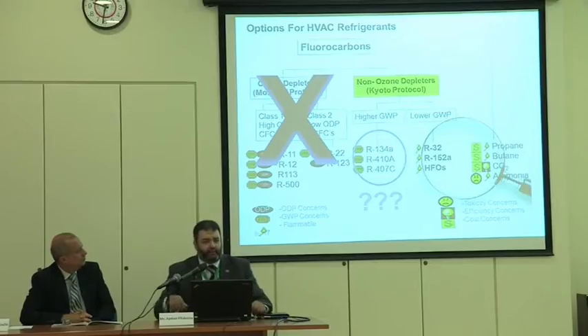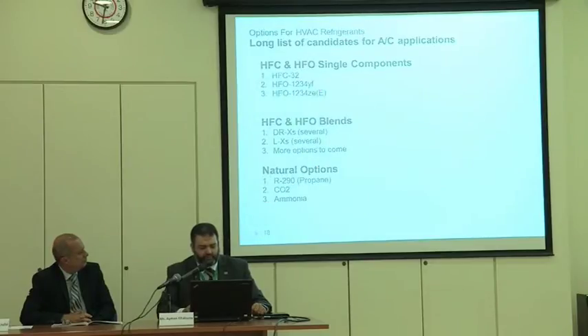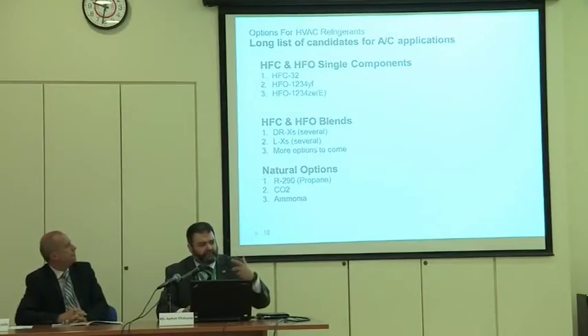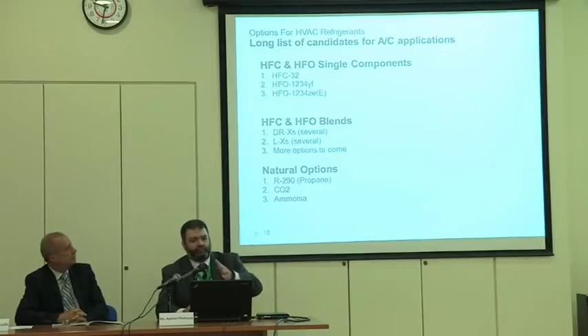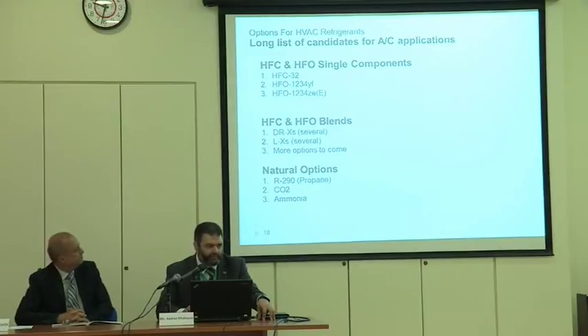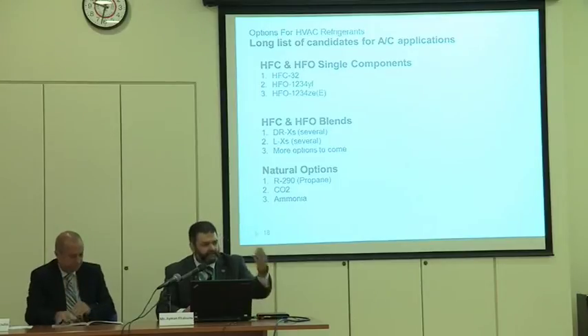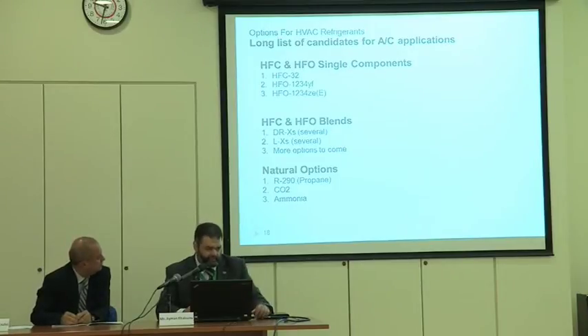So this is the remaining options that we have now. Let's have a closer look at those options. It comprises 3 different categories. A single component category, which includes the 32, and 1234YF, which is not suitable for air conditioning units — it's suitable for mobile air conditioning units, car air conditioning units, and this is adopted by different car manufacturers in Europe now. And something called 1234ZE, and recently 1234ZD as well, which is a liquid refrigerant to replace R11 and 123 for centrifugal large chillers only.